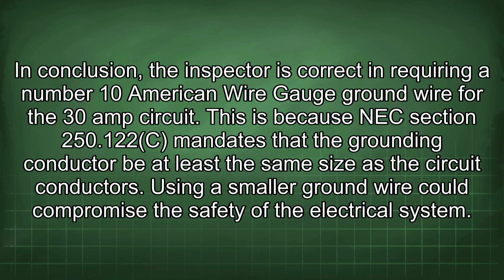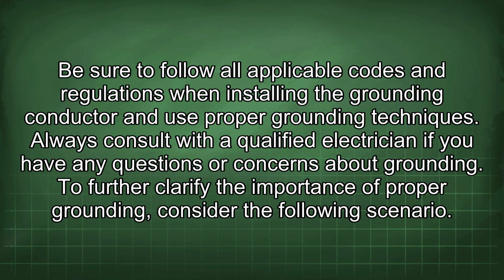In conclusion, the inspector is correct in requiring a number 10 American wire gauge ground wire for the 30 amp circuit. This is because NEC section 250.122(C) mandates that the grounding conductor be at least the same size as the circuit conductors. Using a smaller ground wire could compromise the safety of the electrical system. Be sure to follow all applicable codes and regulations when installing the grounding conductor and use proper grounding techniques. Always consult with a qualified electrician if you have any questions or concerns about grounding.